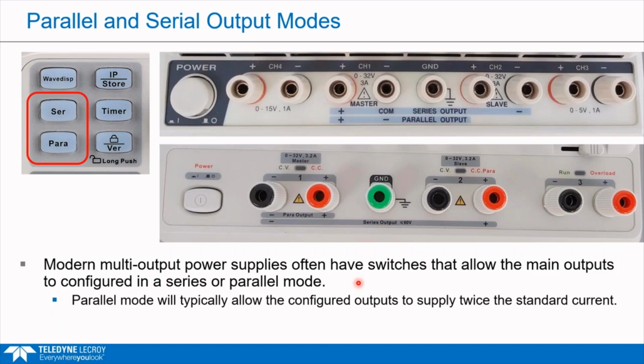Parallel allows the configured outputs to supply twice the standard current. When you press the parallel button, you'll get twice the standard current out of these two terminals - so you've got one output, but twice the current. If it's a 3.2 amp power supply, you'll be able to get 6.4 amps out of here, and that's what I've marked up.